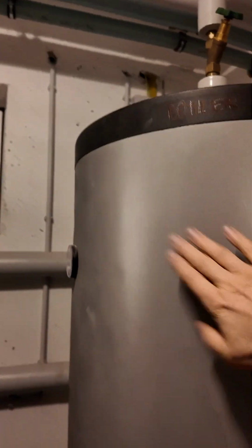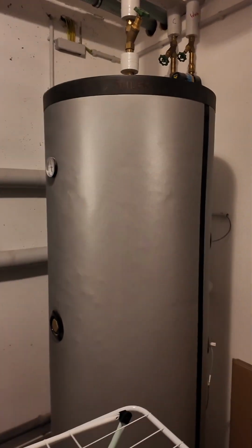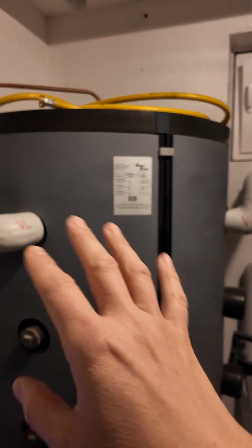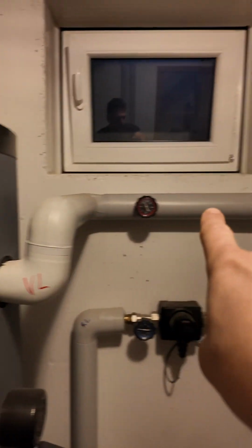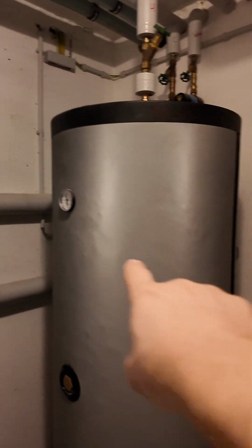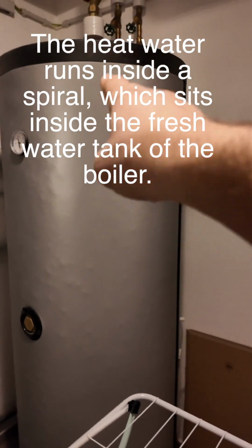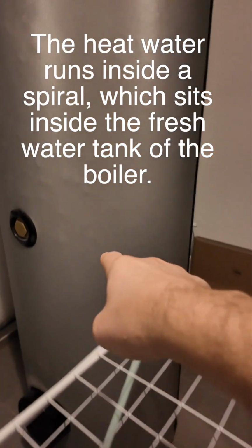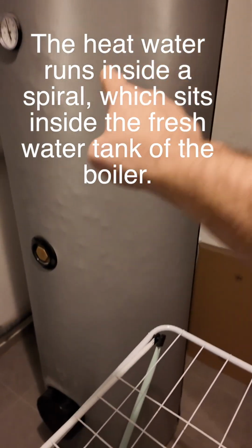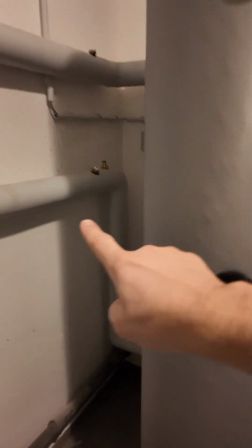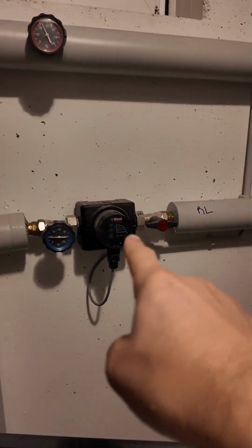Now, how this gets heated up is that you've got the Heizwasser coming out of the buffer there, and it goes to this Vorlauf here, and it runs through a spiral, you know, from the top down to the bottom, and heats up all the water there in the boiler. There, the Rücklauf is coming out of the bottom and going back up this way through that pump. That's how it's circulated and back down here into the Heizwasser buffer.